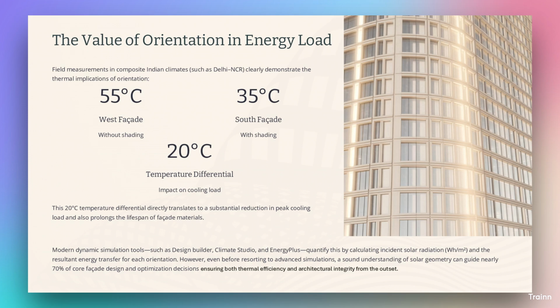The value of orientation and energy load. Field measurements in composite Indian climates, such as Delhi NCR, clearly demonstrate the thermal implications of orientation. 55 degrees Celsius: West facade, without shading. 35 degrees Celsius: South facade, with shading. 20 degrees Celsius: temperature differential. Impact on cooling load.